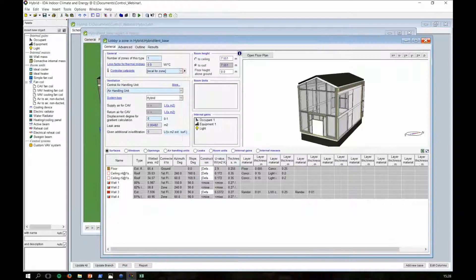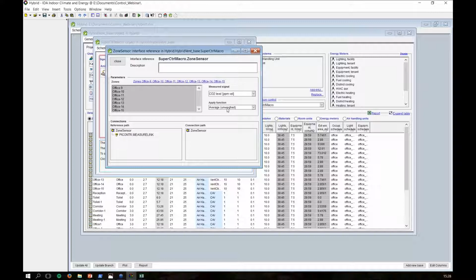The other thing I want to show in this model is using this supervisory control as a branch controller for the VAV systems. So I'm going to use in the supervisory controller my zone sensor to log for several zones the CO2 level in ppm volume. And I'm going to take the average of that. Taking the average of the CO2, I'm going to send a signal to these zones. And using one signal, which averages the CO2 of several zones, I'm going to control the VAV of all these zones.